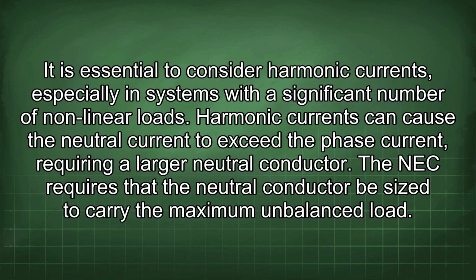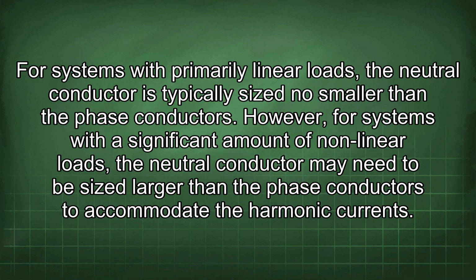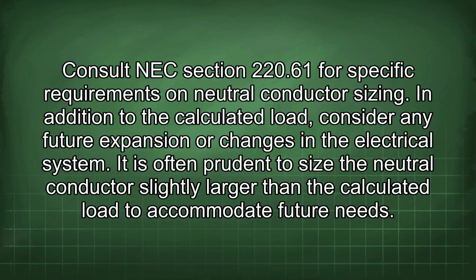Harmonic currents can cause the neutral current to exceed the phase current, requiring a larger neutral conductor. The NEC requires that the neutral conductor be sized to carry the maximum unbalanced load. For systems with primarily linear loads, the neutral conductor is typically sized no smaller than the phase conductors. However, for systems with a significant amount of nonlinear loads, the neutral conductor may need to be sized larger than the phase conductors to accommodate the harmonic currents. Consult NEC section 220.61 for specific requirements on neutral conductor sizing.